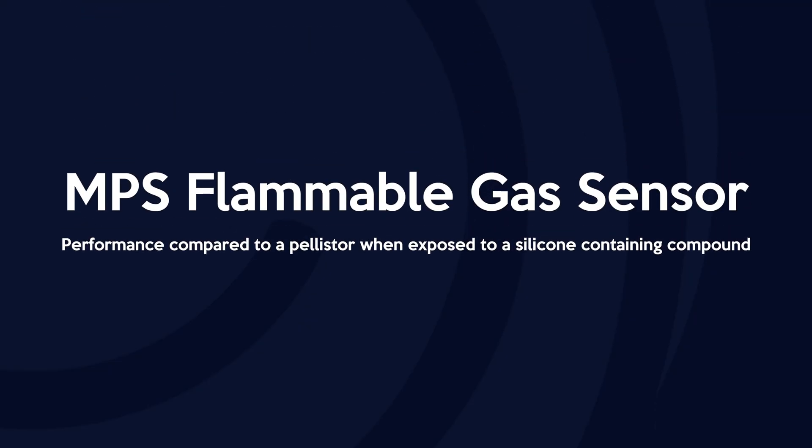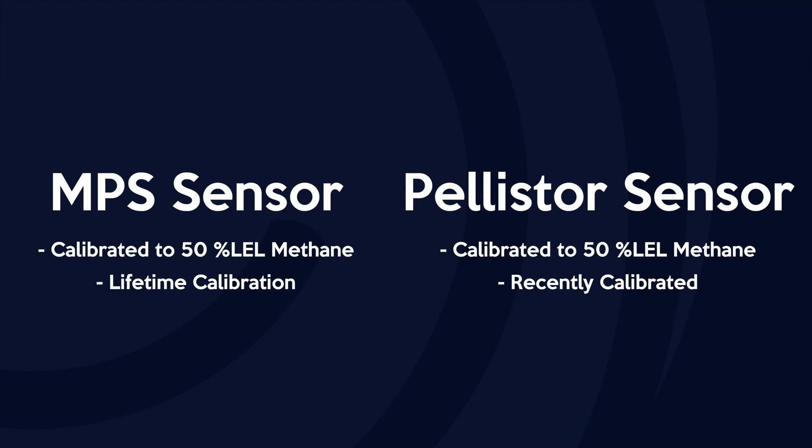Today I will demonstrate the MPS flammable gas sensor performance compared to a pellistor when exposed to a silicone-containing compound. Both sensors are calibrated to 50% LEL methane. The MPS is calibrated once in the factory and does not require recalibration for the full lifetime of the sensor. The pellistor was calibrated just prior to this demonstration.